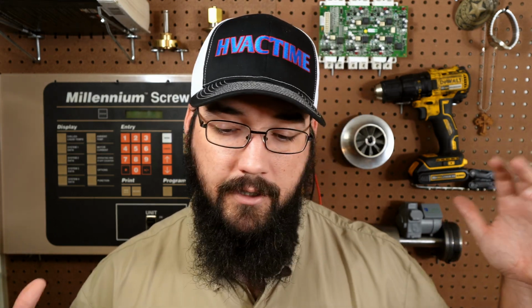And when I've had them fail, typically they'll do some kind of overcurrent. Then they'll fail one of 2 ways. Either they'll fail, and like say with a soft starter, I had one call where it was showing a phase loss at startup, because one of the SCRs had failed and it wasn't passing power through properly. It may show an overcurrent or a phase imbalance. So maybe it can close, but it's not opening properly. So the others are working and they're trying to bring it up slowly, but this one just slams shut. That's going to cause an overcurrent or an imbalance in the current. Or my favorite, they just blow up. Genuinely, SCRs, when they fail, they just grenade into 1,000 pieces, and you just don't want to be there when it happens. So that's one of the dangers of working with that level of equipment. It is very dangerous to touch, be around, be cautious, think about those things.